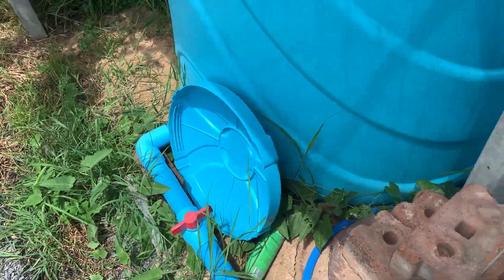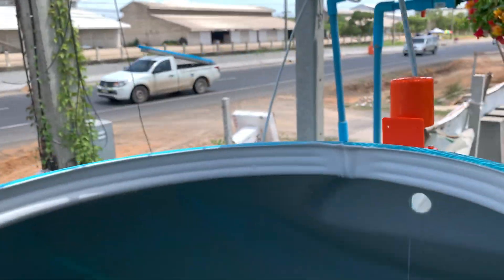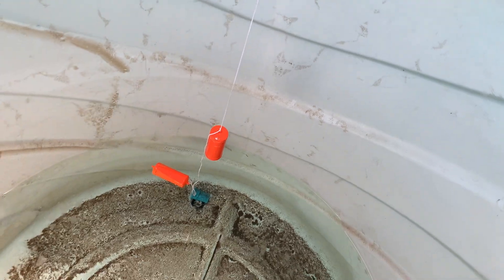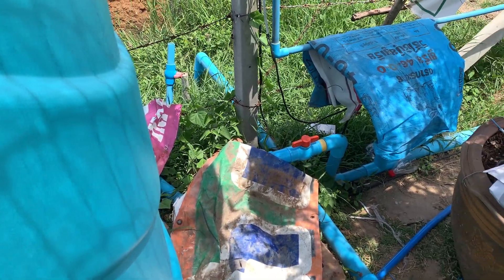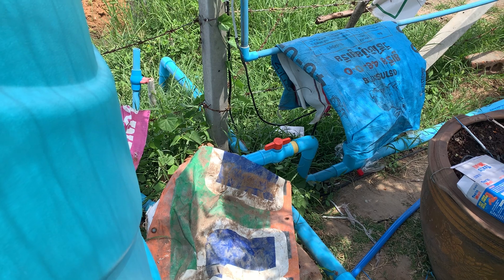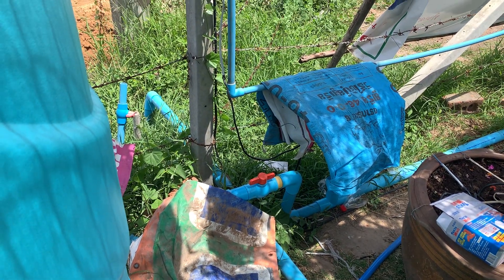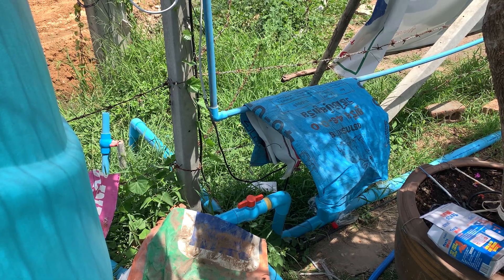So I've turned off one of the tanks and the idea is now to let the one drain out while the other does some water in, and we can actually give it a proper test. The first one is already out of the water and the second one is nearly down at the bottom. Probably another five minutes and we'll be able to see it actually working in process - it should cut out the power to the pressure switch and obviously the pump. I'll add the videos in as well so we can see how it actually really works.